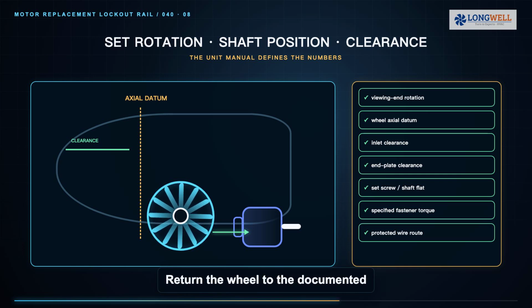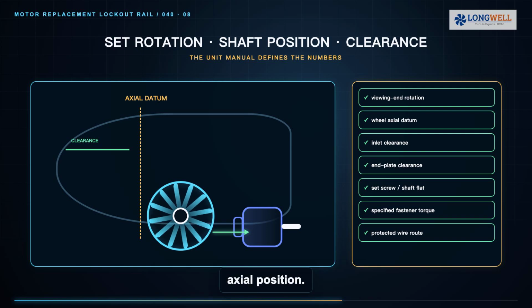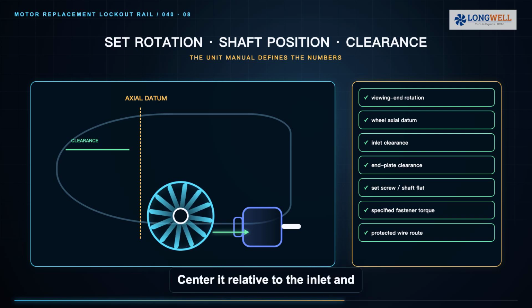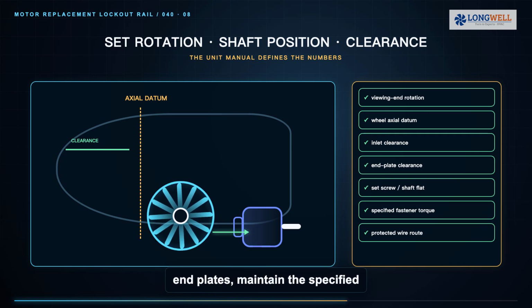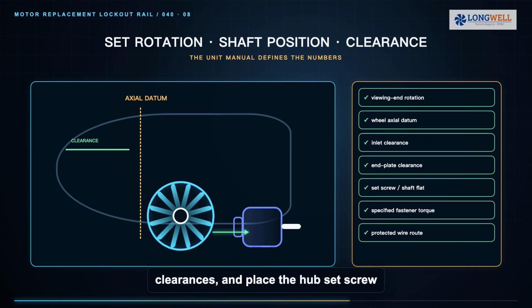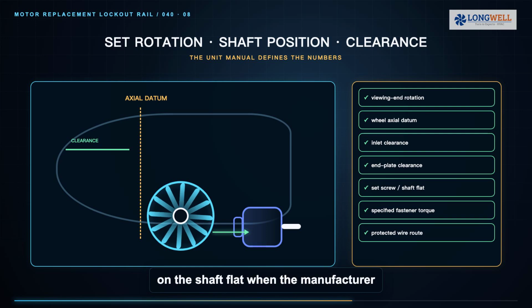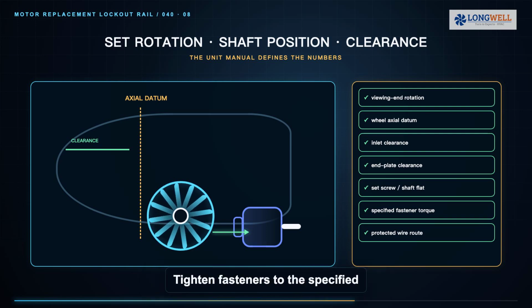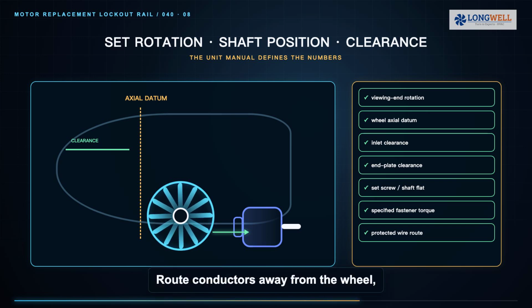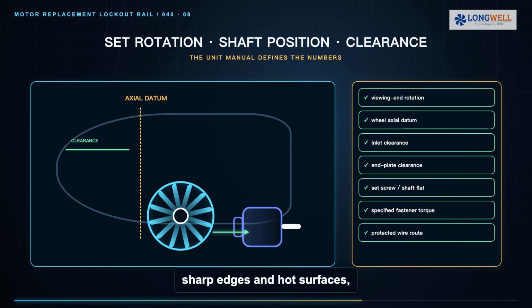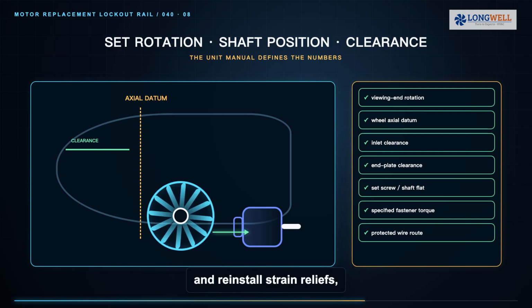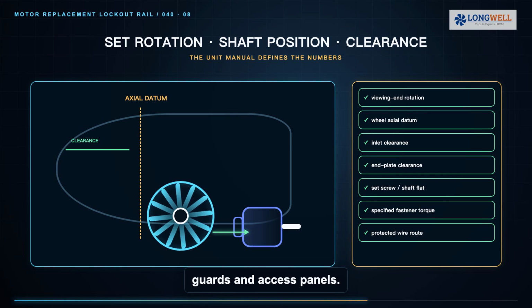Return the wheel to the documented axial position. Center it relative to the inlet and end plates, maintain the specified clearances, and place the hub set screw on the shaft flat when the manufacturer requires it. Tighten fasteners to the specified torque. Route conductors away from the wheel, sharp edges and hot surfaces, and reinstall strain reliefs, guards, and access panels.